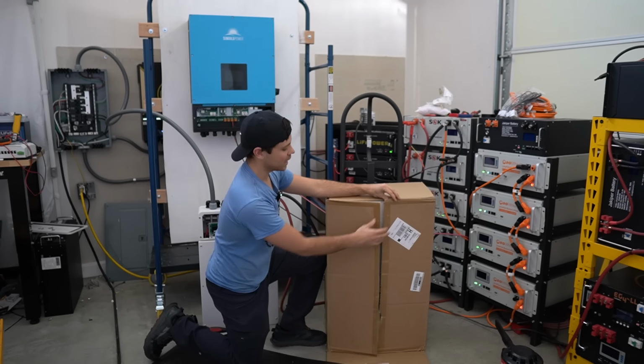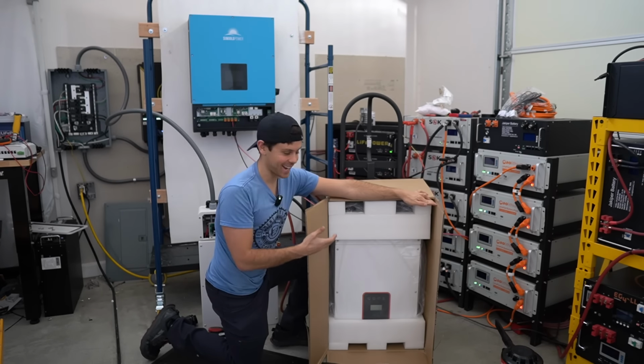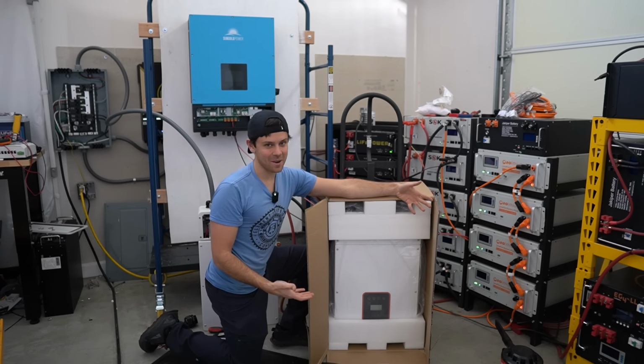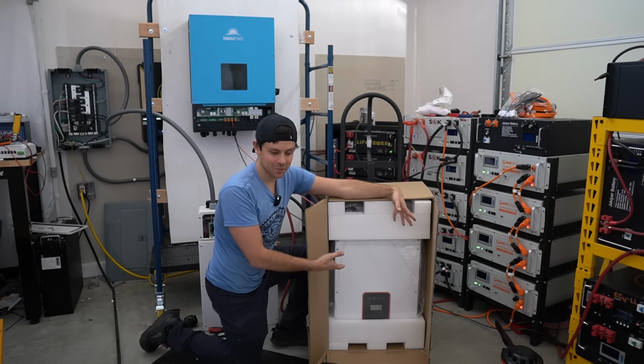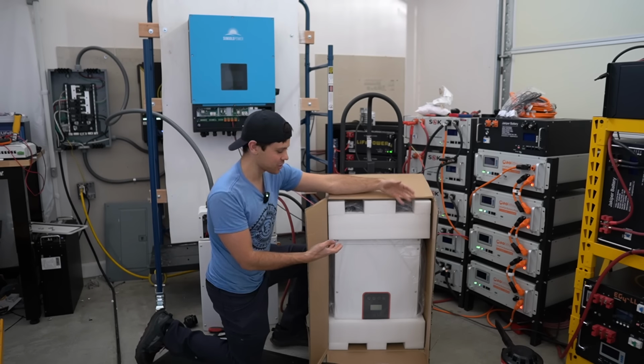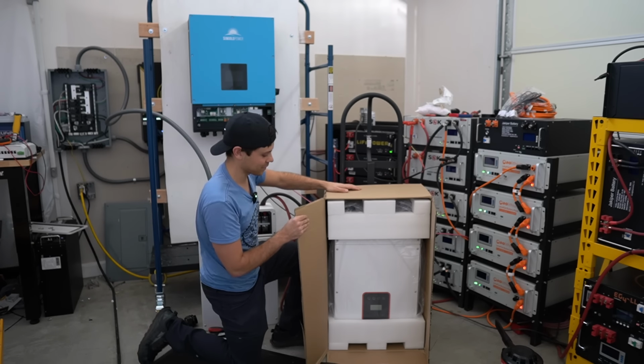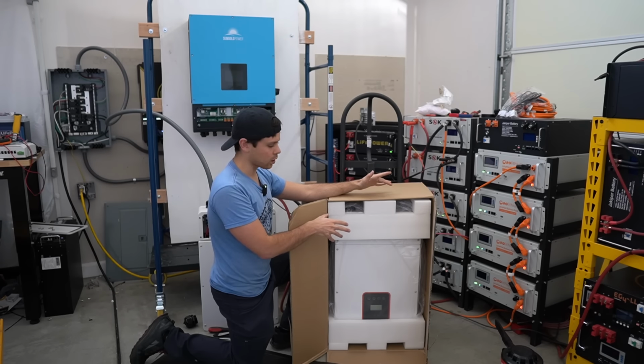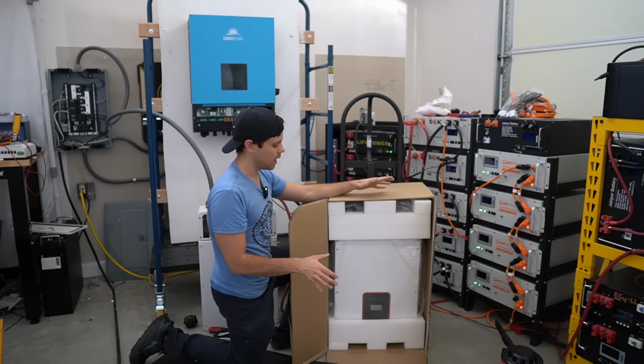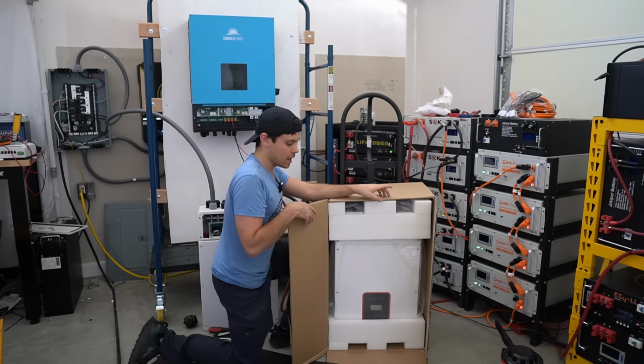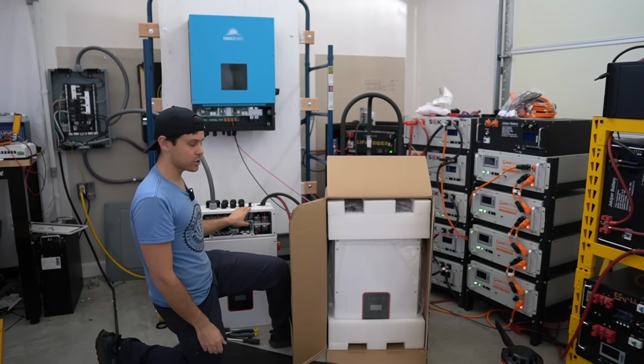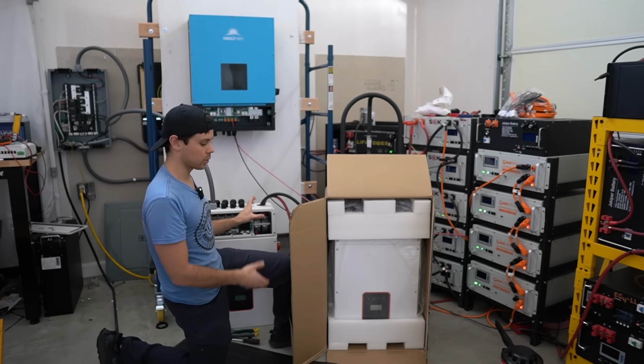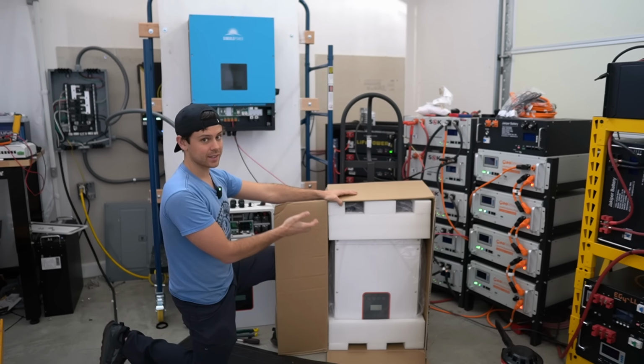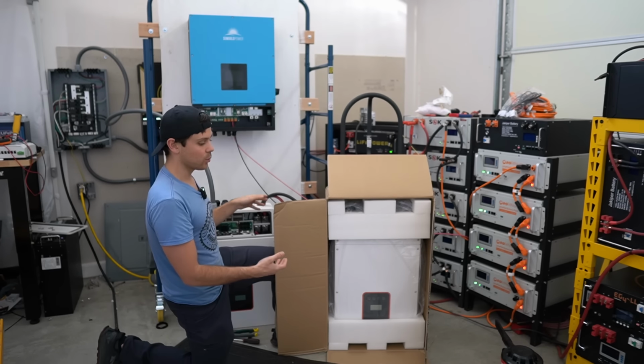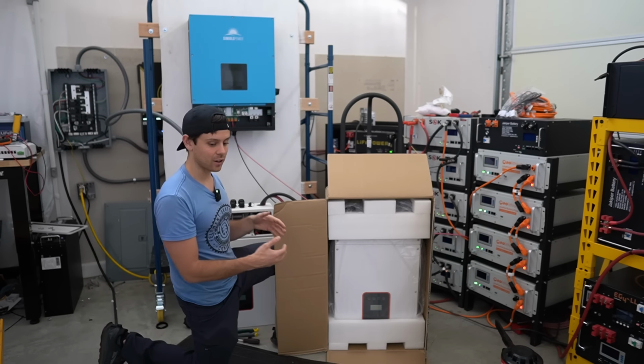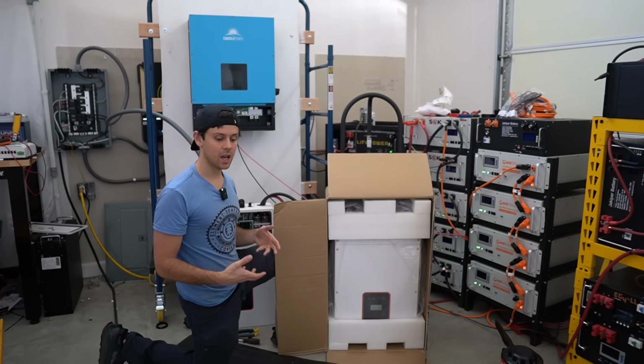But this morning, a Chinese company sent out the exact same inverter. I don't even know what company this is. So we're gonna fire this one up and see if it has the same exact issue as the Signature Solar 8K inverter. Now, if this new inverter does work without changing any of the settings and having the GFCI enabled, then that would mean that there's a quality control issue in here and there's some leakage going on in the board or something funny. Now, if the new inverter has the same exact issue as this one, then we're gonna have to go through all of the settings and figure out what's wrong because there has to be something that I'm missing.